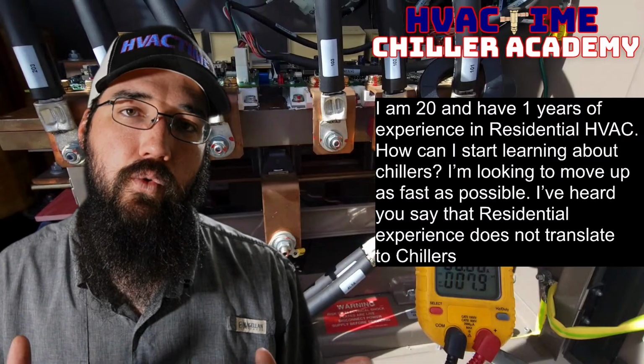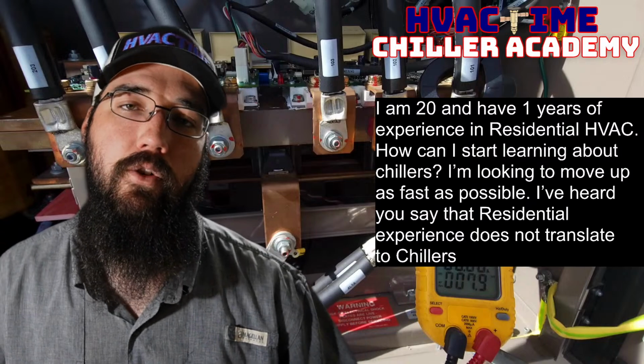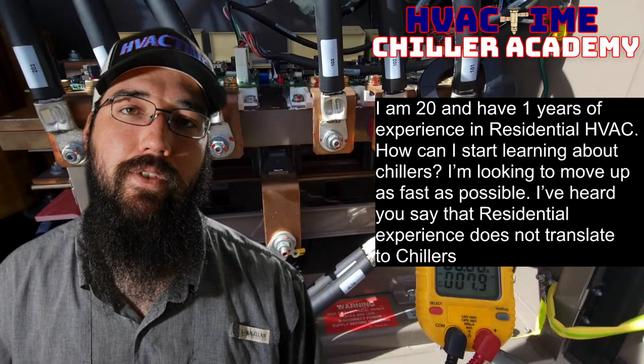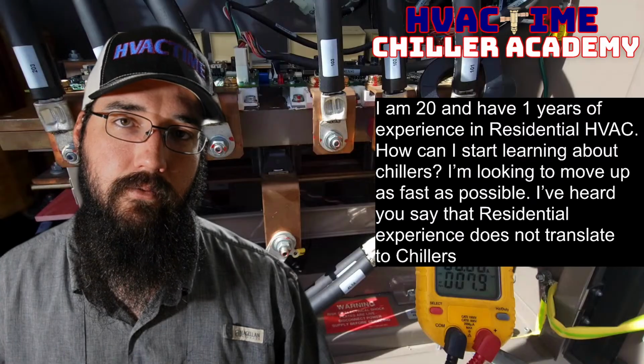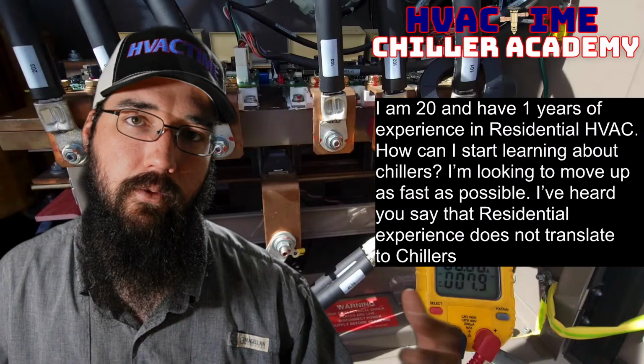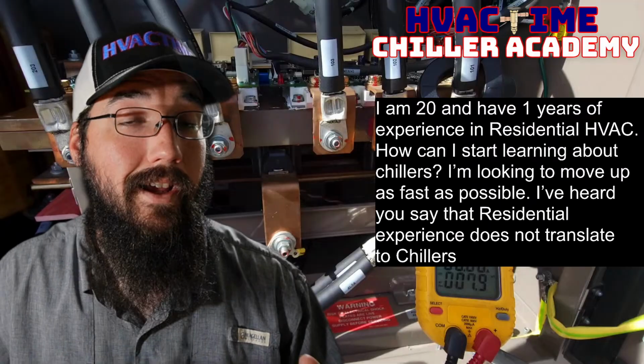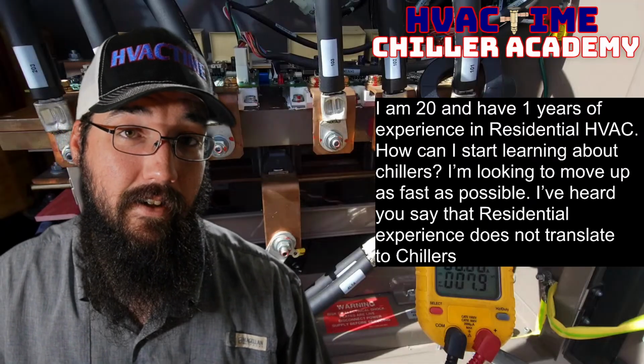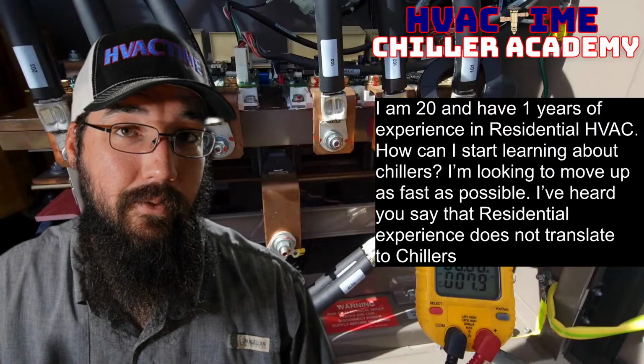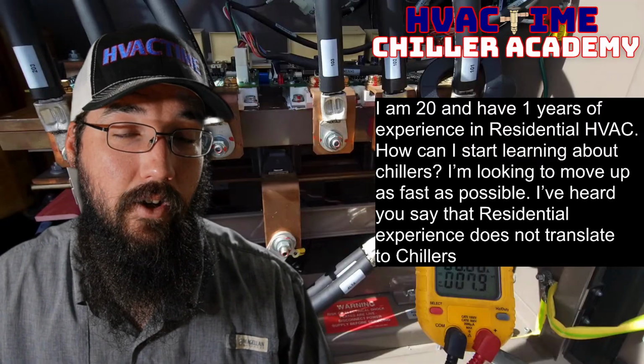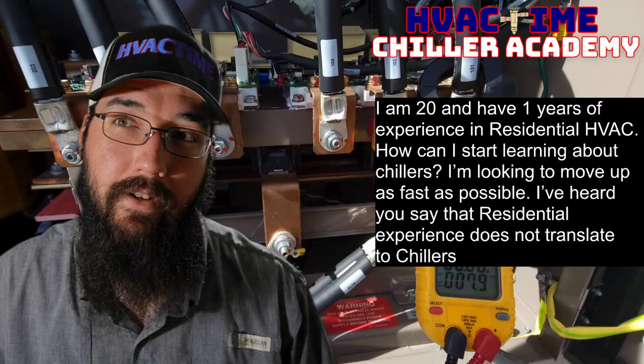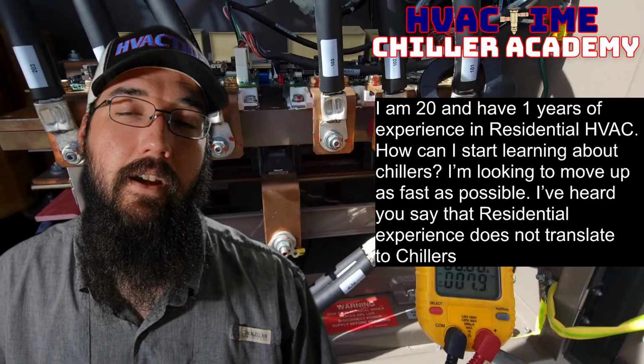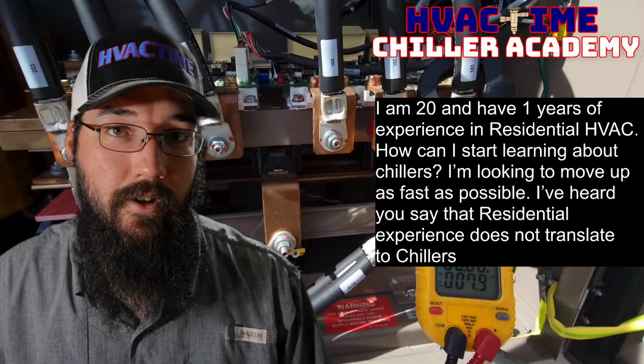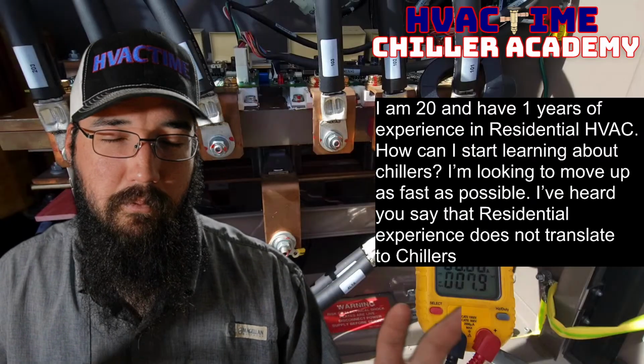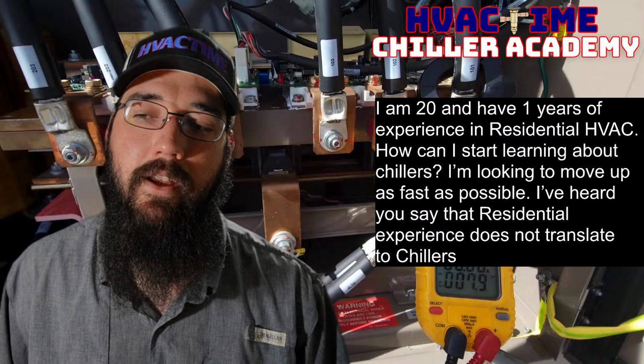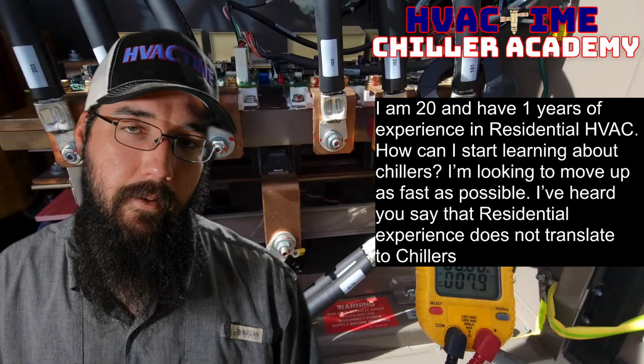But we use water through a chill water coil the same way that we would use DX coils, right? Which is just a refrigerant-based coil, with refrigerant flowing through the coil instead of water. I will point out, real technicality here, water is a refrigerant. Was it 718, I think, is the R number? Pretty sure that's right. 718 or 713, something like that. It has a refrigeration R number. That doesn't really matter in this context. Point is, we use it the same way.